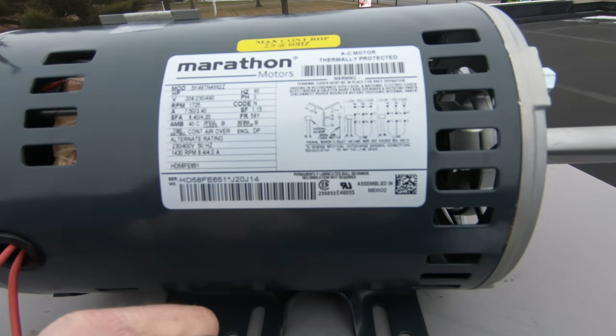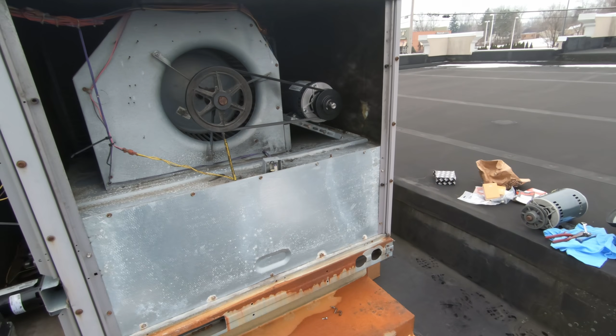Got the motor and pulley all adjusted, got my wires pinned back up. I'm going to check the amp draw on this before I do anything else. That way if I have to make adjustments to that pulley - the old pulley seemed like it was way too wide, I don't know why they went out so wide, it was unscrewed way out, so I didn't set it exactly there. Our amp draw on the motor should be 7.5, so I'm gonna get the panel put back on. I want to run this motor now, check that amp draw, and get my pulley set if I need to adjust it now before I get into anything else.